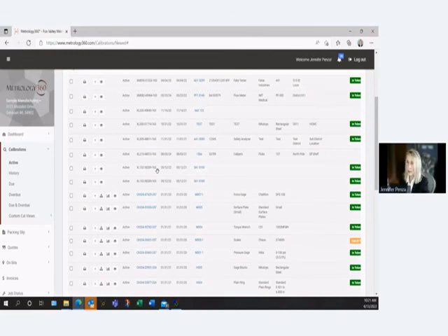The next thing we're going to go through is the fact that if you have put in any certs with an X, you are going to be missing these little action icons. You're going to be missing the traceability and the wear analysis chart simply because the data does not exist on our end for anything you've calibrated on your own or sent to a third party.